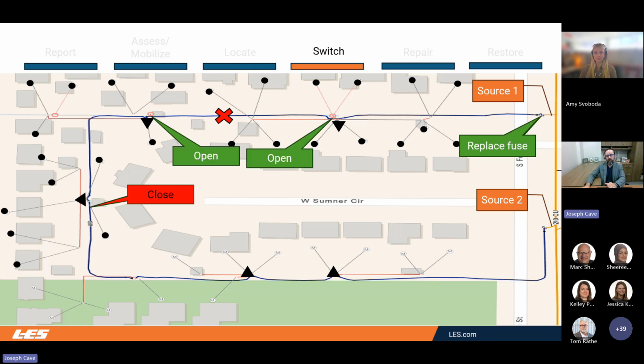So the next step in the process is to switch around the failed equipment. So the troubleshooter will first go over to the transformer on the left, and they'll open a point on the system so that it is no longer connected to the point of the failed equipment. Next, they'll go to the adjacent transformer and open up the system there. And then finally, they'll go to the transformer off to the left where you see the close sign there, and they'll close that normally open point to restore all of the customers on the left-hand side. So you can see source 2 feeds through there, goes through that now closed switch on the system, and restored power to all of the customers on that side of the failed equipment.